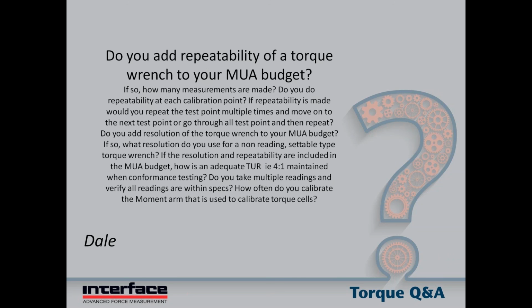I'm not going to actually read this entire question, but to address it, we're doing a torque wrench calibration. Interface does not calibrate torque wrenches. In fact, we send our torque wrenches out to a local shop to get calibrated. That said, we are involved in the metrology side of torque measurement and do offer torque transducers that are used to basically check or calibrate machines that are used for torque calibration or torque wrench calibration.